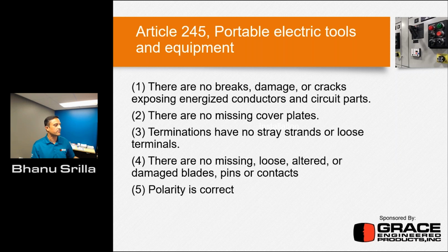Okay. So Article 245 talks about the portable electric tools and equipment. You need to make sure these 5 things are checked, because portable electric tools are one of the things which industries use on a regular basis, more frequently, right? So there are no breaks. You need to make sure you check the cord and plug equipment. There are no missing cover plates. Terminations have no stray strands or loose terminals. There are no missing, loose, altered or damaged blades. And also make sure the polarity is correct, right? So whenever you use these cord and plug disconnects or portable tools, you check the cord, insulation, strands and everything, that they are intact before you use them, okay?